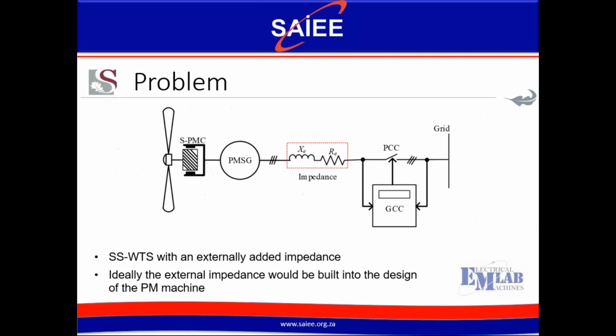Wind, yes. Typically, direct grid connected synchronous generators aren't really the way that wind turbines are constructed. Typically, the generators, especially permanent magnet generators, are connected to the grid by means of a full rated converter. One of its responsibilities is to damp the fluctuations caused by the wind that oscillate through the drivetrain. But for the slip synchronous generator, the slip permanent magnetic coupling, if I can go back to this slide, it is responsible for damping the fluctuations caused by the wind. It operates similarly to a permanent magnet induction machine, where the slip function dampens those oscillations.